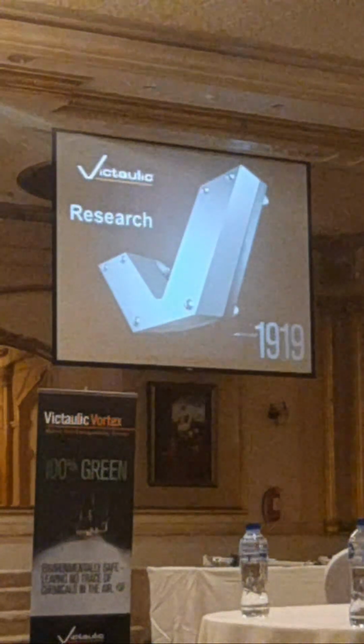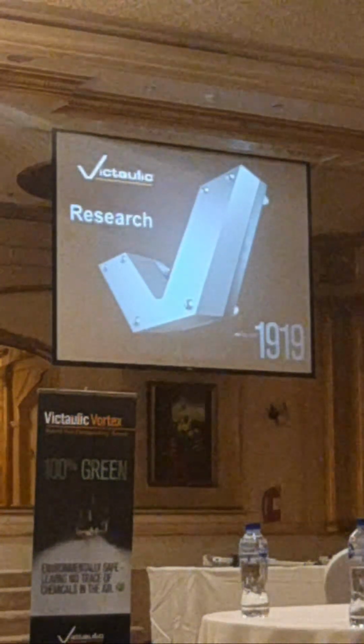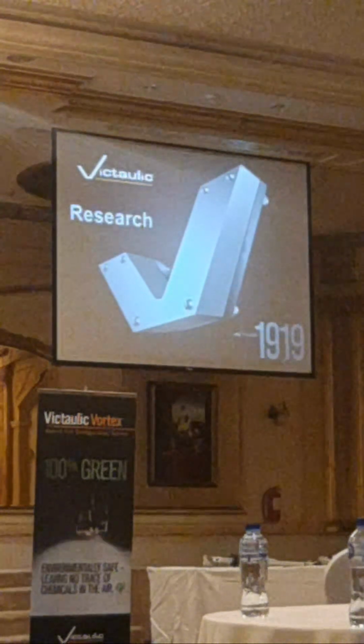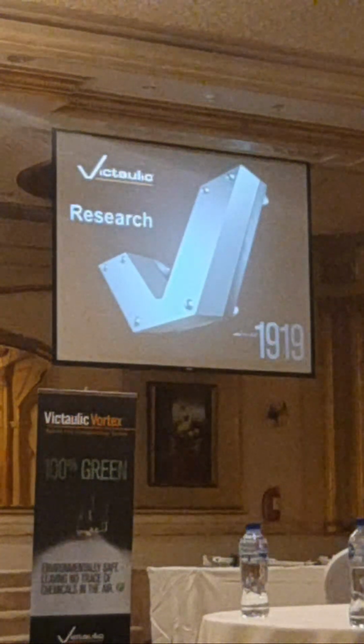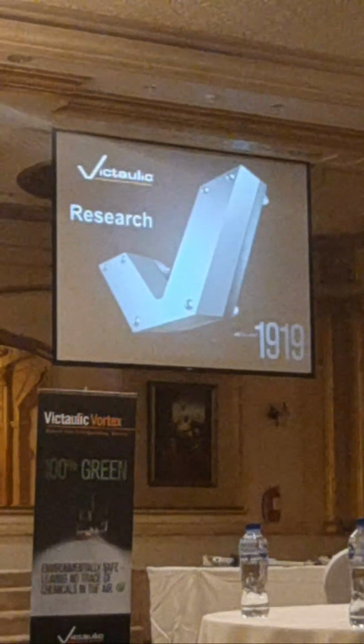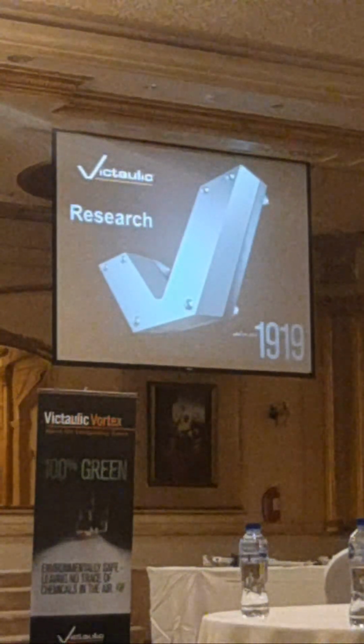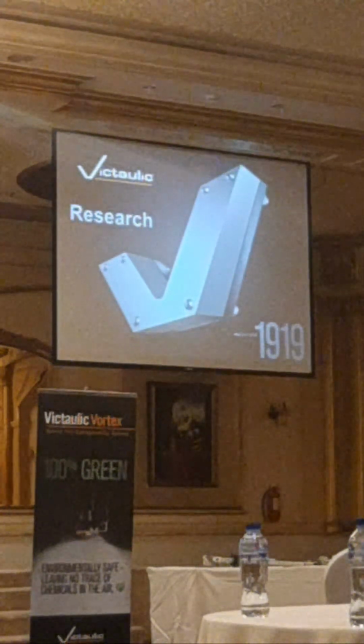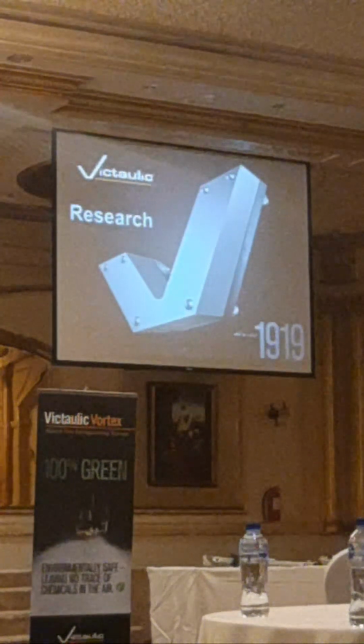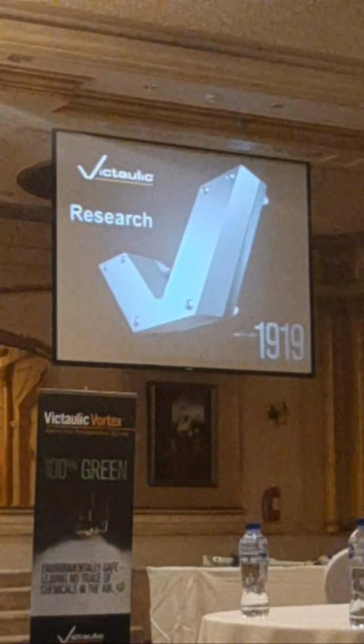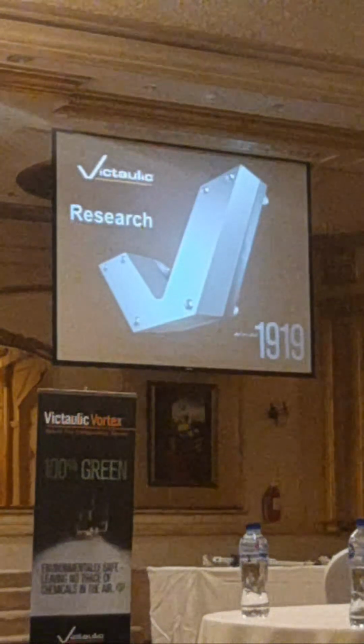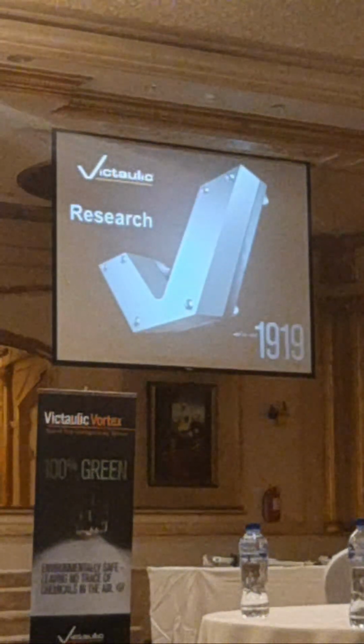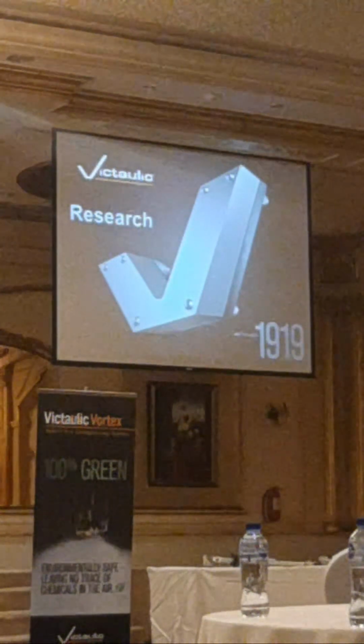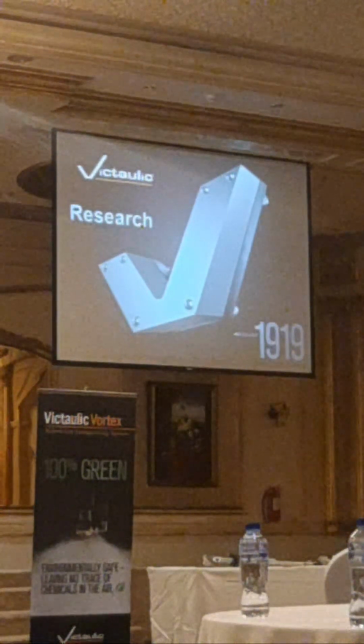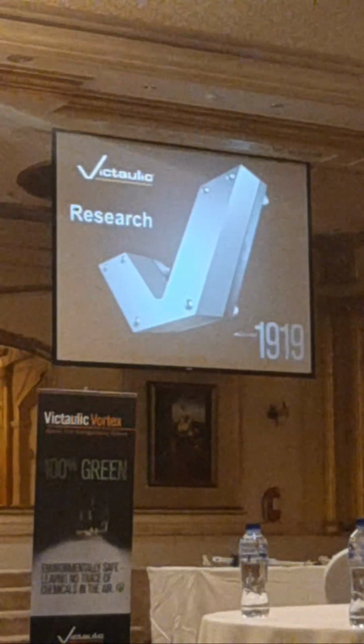How does it change, for example, from a Marioff system? A Marioff system sometimes also uses nitrogen, but they're using it as a propellant to push their water - their cylinders are just a replacement for a pump. The amount of cylinders they have will never be enough to bring the oxygen level down, so they're just using it to bring water to the nozzles. That's why they're considered a twin fluid system in the NFPA 750, which is different from hybrid.